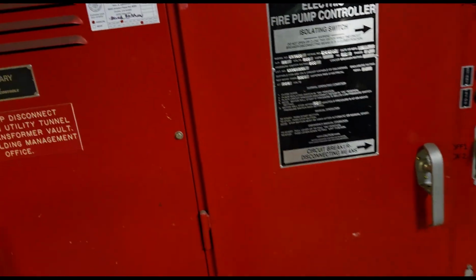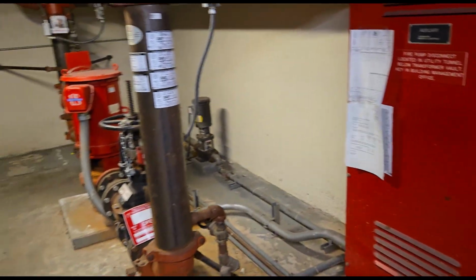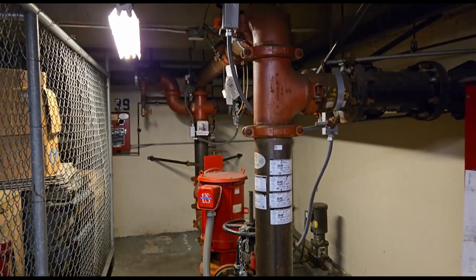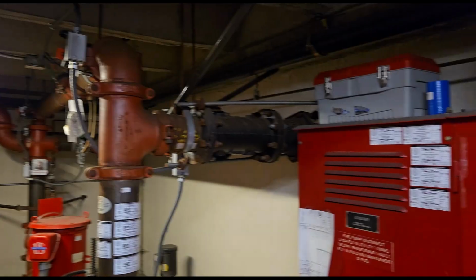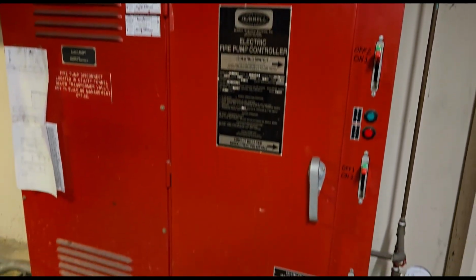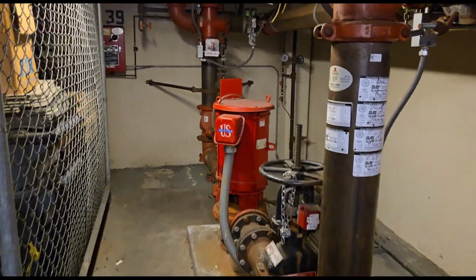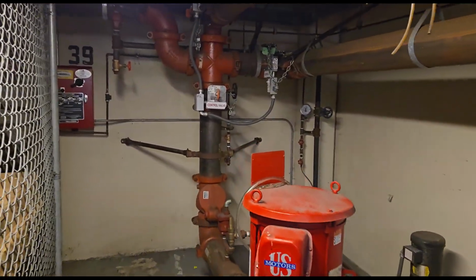The reason why we turn it off is because for this particular client, they only have an alarm contract with us, they don't have a sprinkler contract. So we're not taking liability for their pump, so we're going to turn the pump off. Their sprinkler company is responsible for testing the fire pump. So all I'm going to do is be testing the switches and valves, making sure that the electronics work and report to the fire panel.